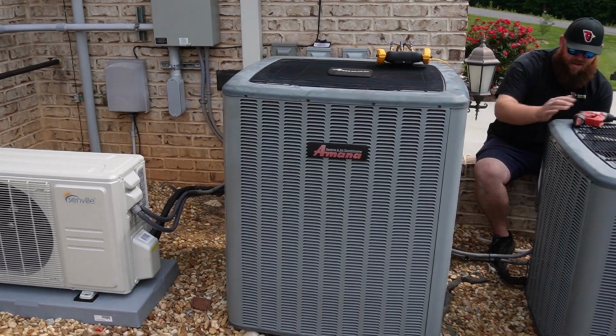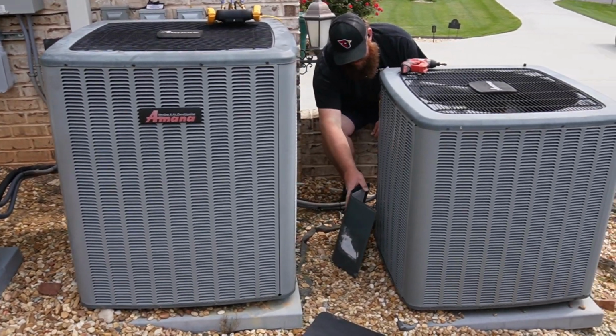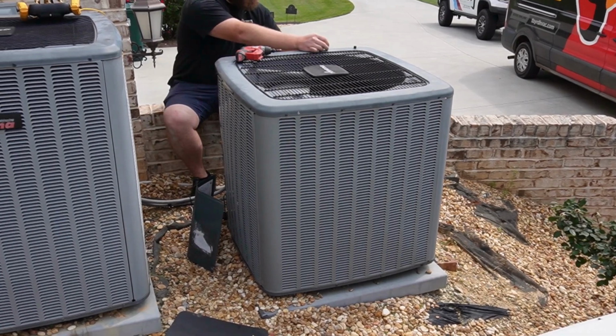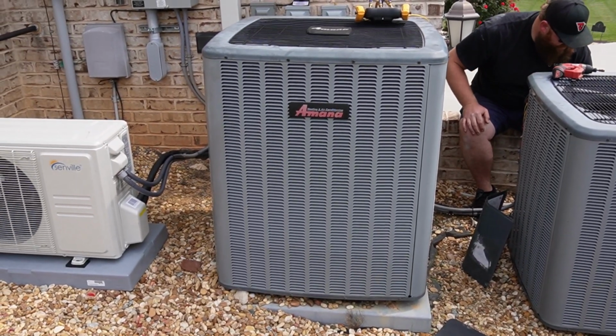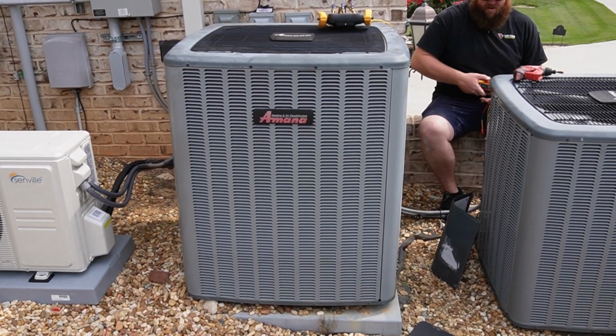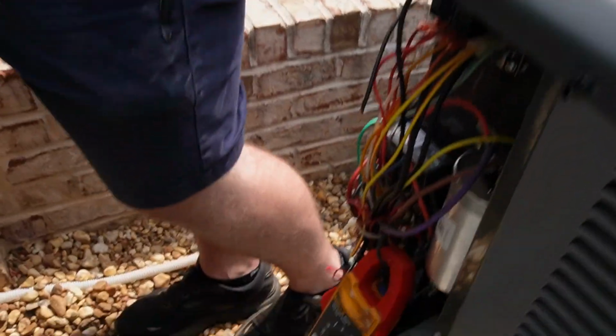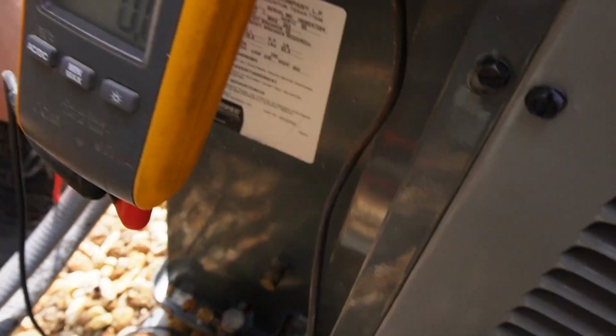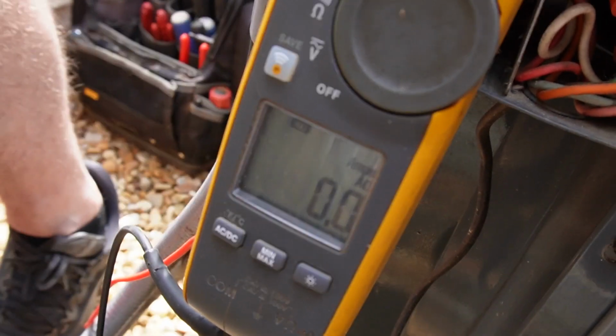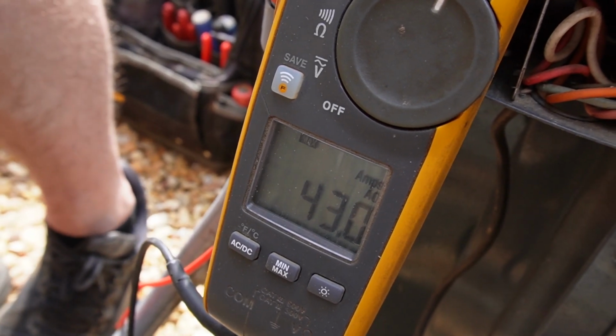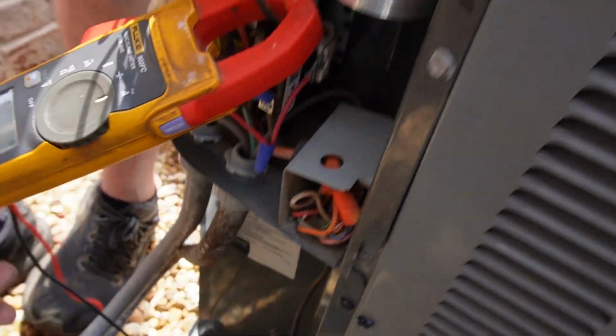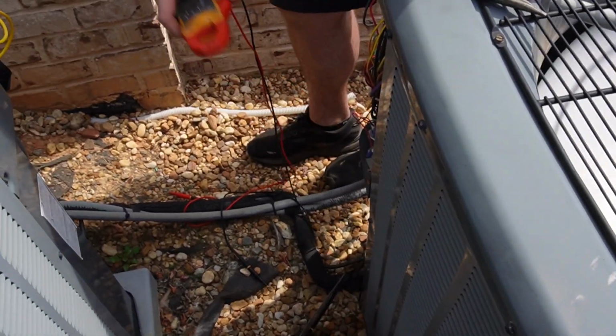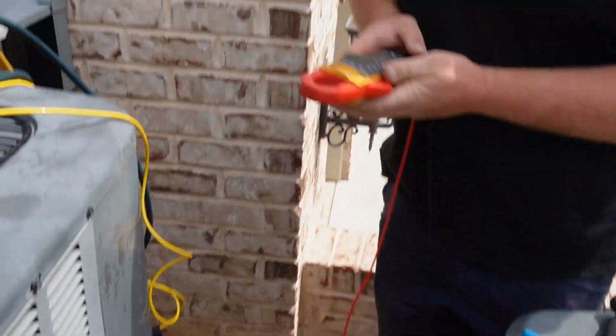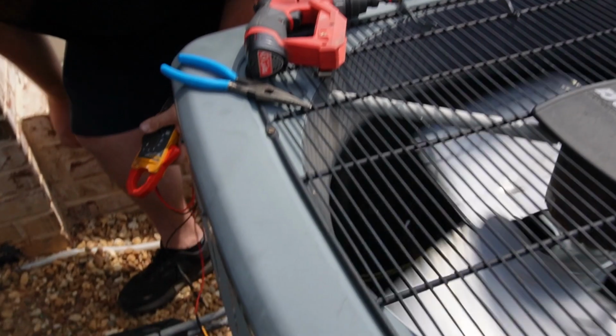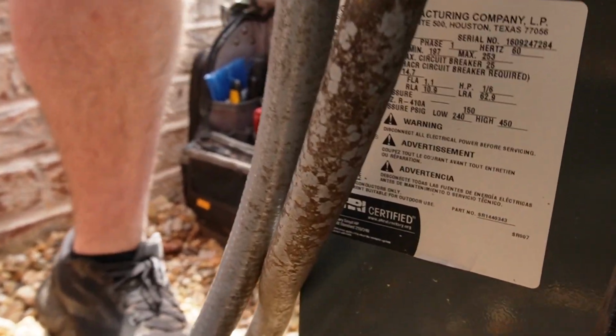As far as the regular maintenance goes, we've got 2 Amana units. One's a split heat pump, one is a split system that is hybrid, heat pump and gas furnace. All right, so you see here Josh has the clamp from Fluke hooked up. We're gonna test our inrush amps on the compressor. On this type of meter, it does save, so it locks out and gives us a reading. So we were at 43 amps. 43 amps. 62.9.